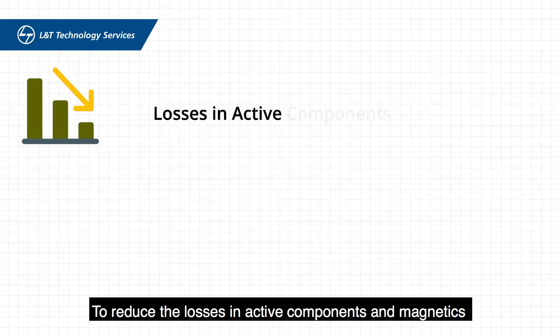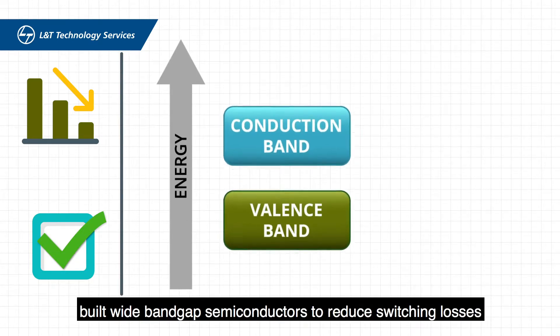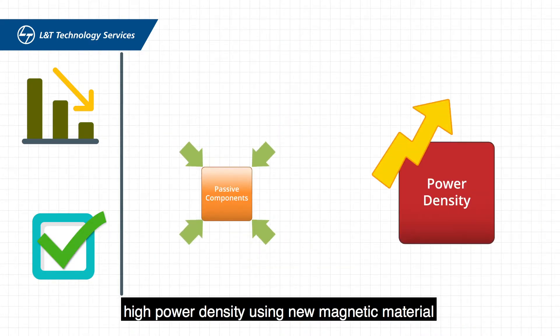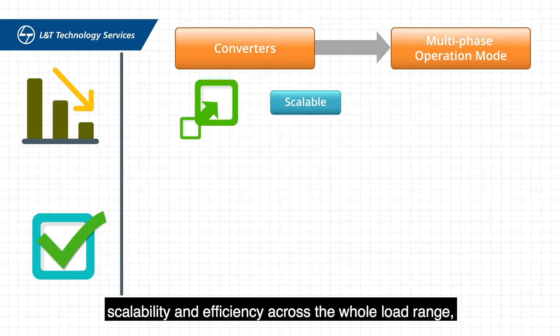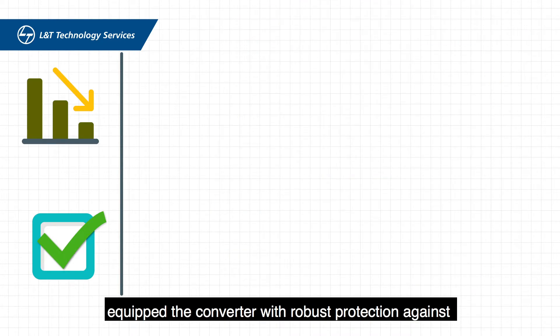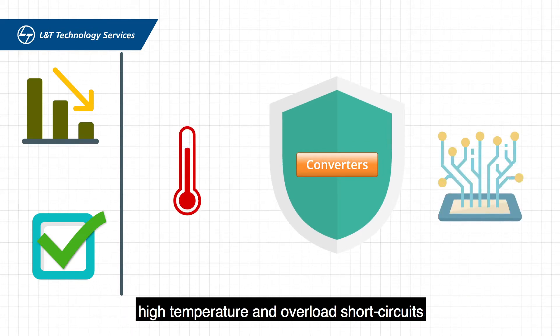To reduce the losses in active components and magnetics and resolve thermal issues using appropriate cooling techniques, we built wide bandgap semiconductors to reduce switching losses, reduced the size of passive components, and helped achieve high power density using new magnetic material. We used the converters in a multi-phase operation mode to ensure scalability and efficiency across the whole load range, while reducing ripple currents in the capacitor, and equipped the converter with robust protection against high temperature, overload, and short circuits.